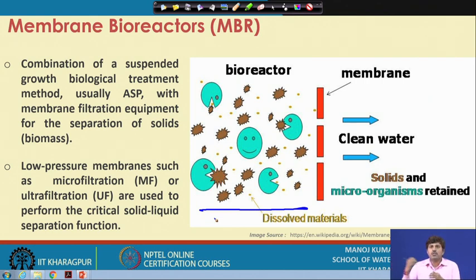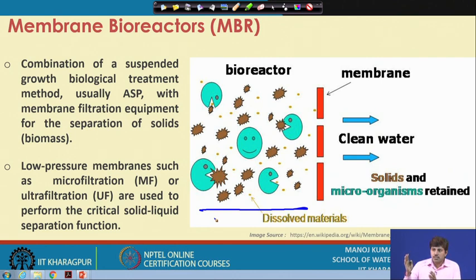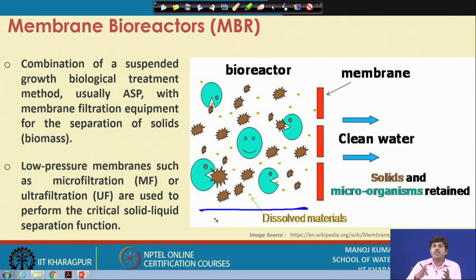Because the secondary clarifier may not be very efficient, we may still get some solids washing out in the effluent, and we also have to recycle the sludge back to the activated sludge system. In a MBR, instead of going for a secondary settling basin, a semi-permeable membrane is put in place which allows water to pass through but retains the solids. Since we are dealing with wastewater, high-end membranes like RO or nano filters are not used — instead, microfiltration or ultrafiltration membranes are used.